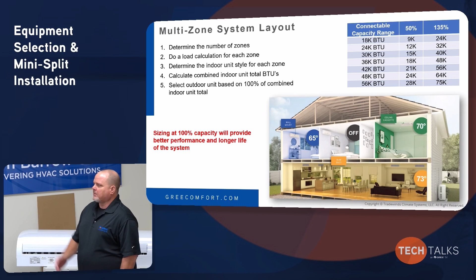And also, don't forget, select the outdoor unit after you have selected your indoor units. So you do your zone by zone load calculation, you determine how much you need inside, and then you select the outdoor that fits that. We want to size at 100% if possible to provide better performance and longer life for the equipment. We don't want to oversize it too much, because then when all zones are calling, you may have one that's only getting 3,000 BTUs on a 9K because every other unit is calling as well.